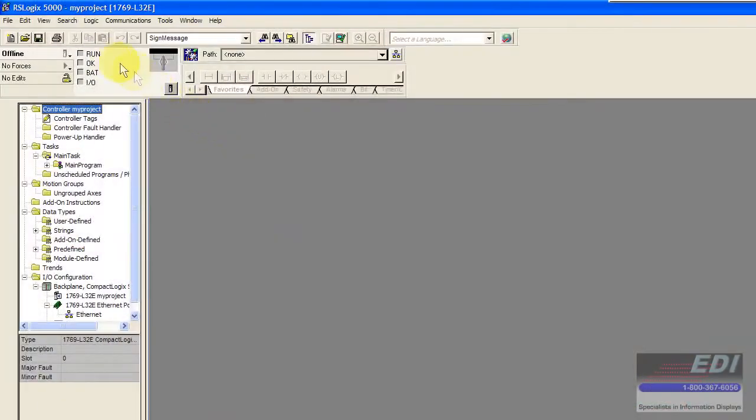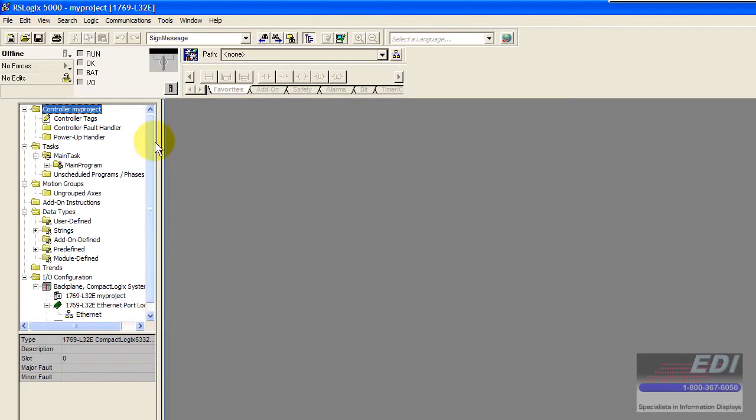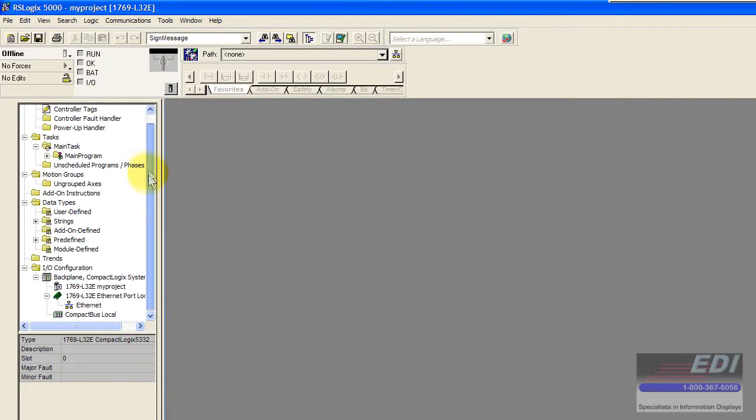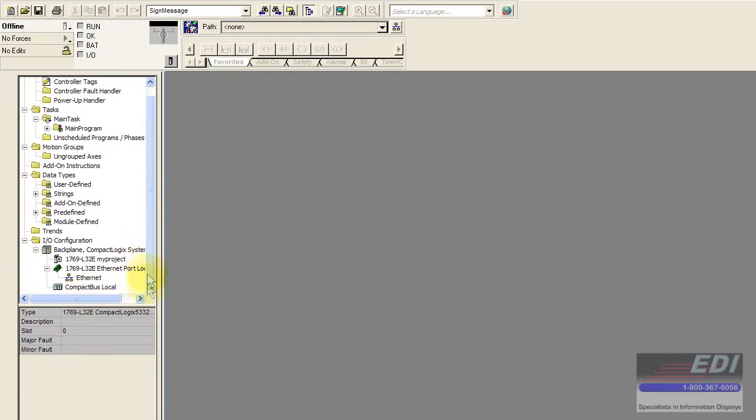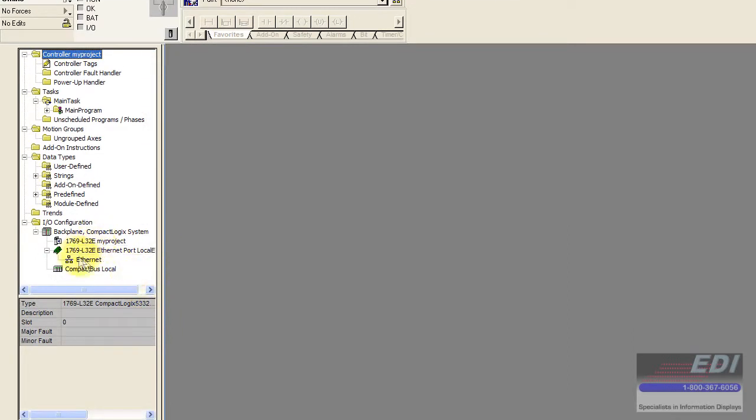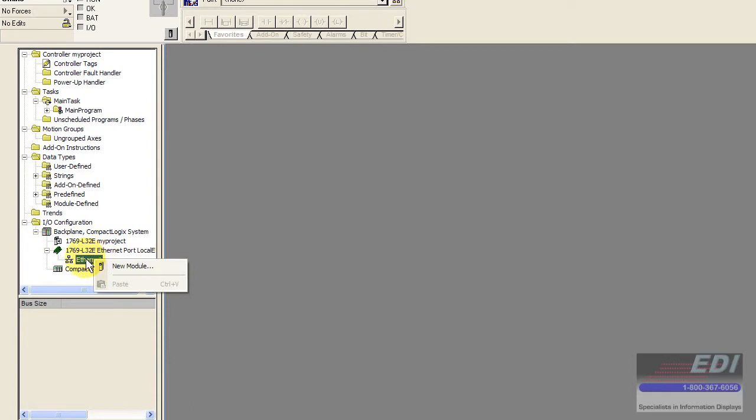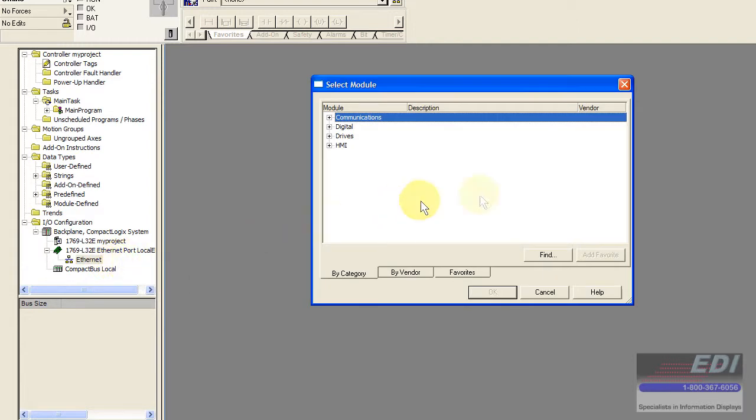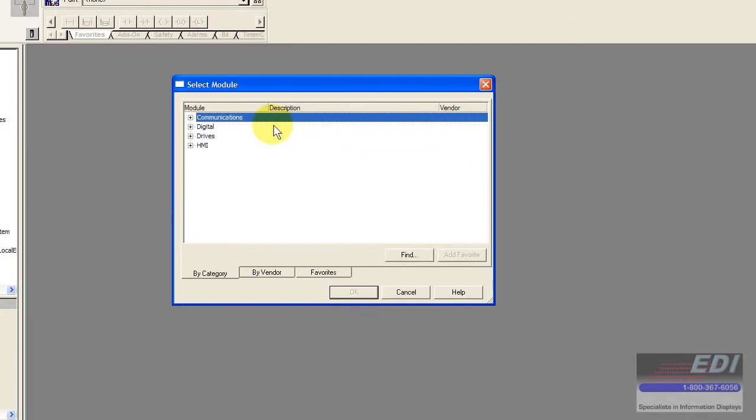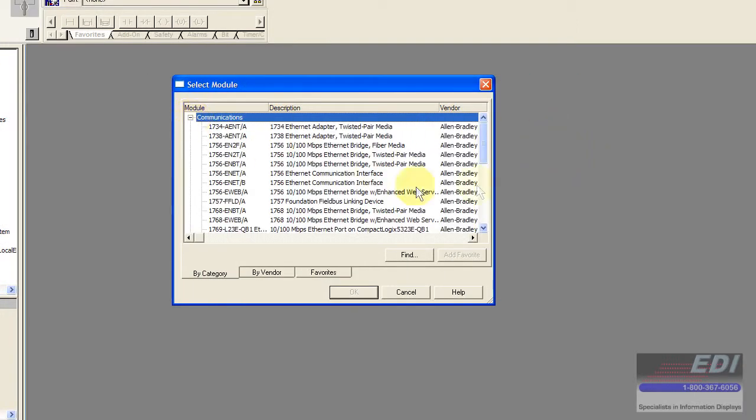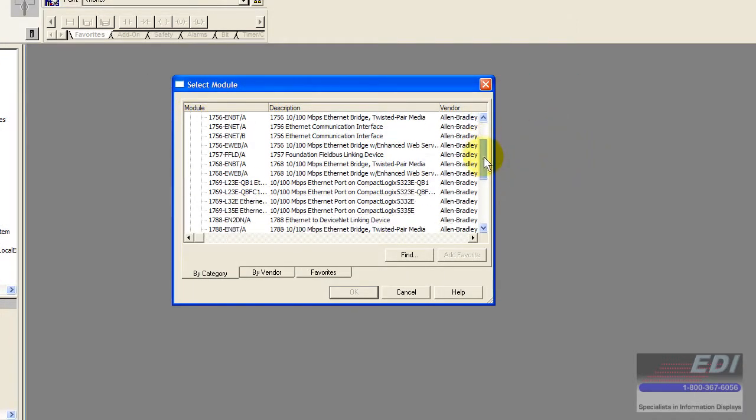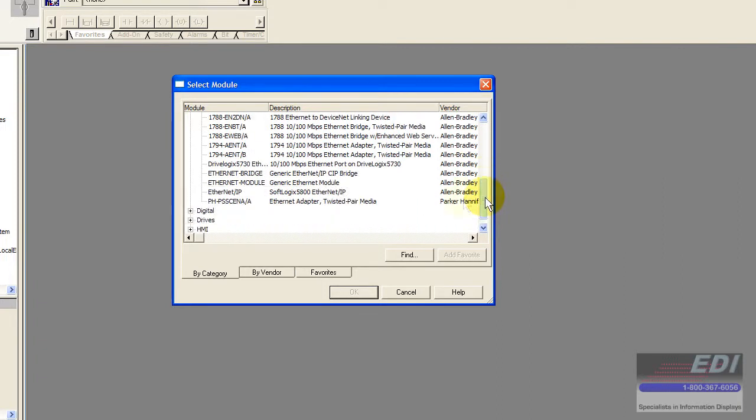In order to fix that we're going to configure what's called a generic ethernet module between the PLC and the AnyBus communicator. Right now I don't have any IO on my CompactLogix, it's just a processor only. Off of the ethernet port I want to configure a new generic module so I'm going to click on new module, then go to communications, and browse down until I find the generic ethernet module.